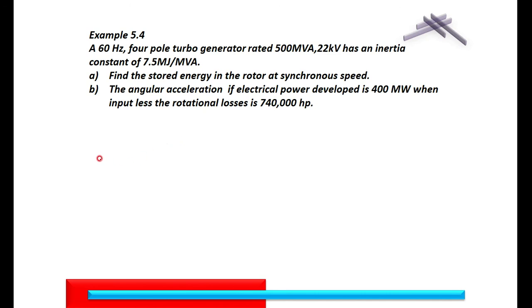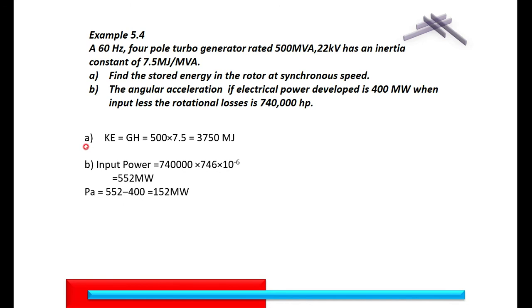We will find the stored energy. The stored energy is given by S times H, which is straightforward. S is given as 500 and H is given as 7.5, therefore the stored energy is 3750 MJ.